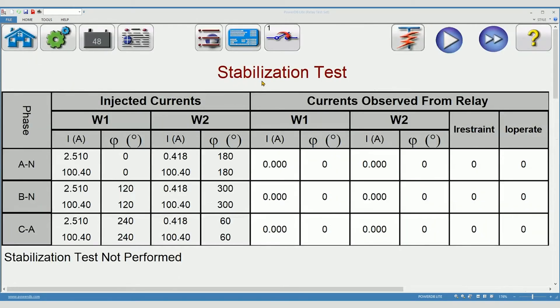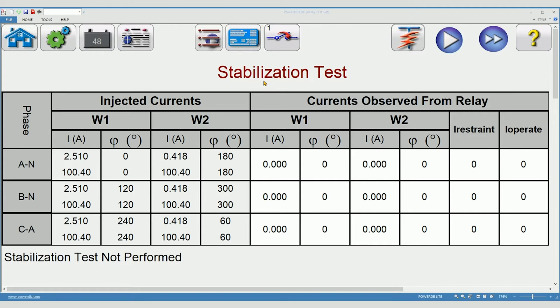A stabilization test verifies the relay will not operate for a through fault. It also verifies your test connections and allows you to verify the metering function of the relay. When you're ready to proceed, press the play button.